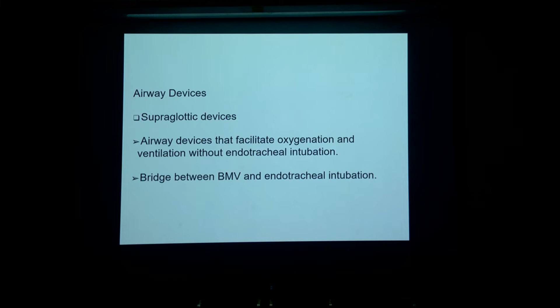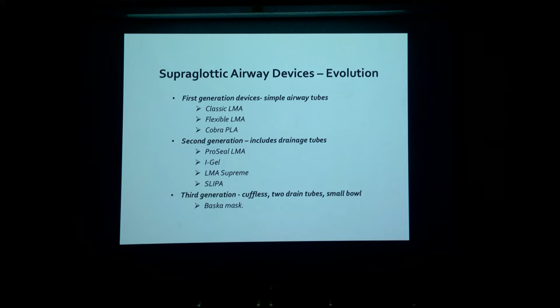The 2nd generation was an improvisation of the 1st generation, wherein disadvantages like gastric insufflation and not being able to decompress the stomach were addressed. And 3rd generation is further better. The advantage of the 2nd generation is that these devices can be used for positive pressure ventilation. But the disadvantage is that positive pressure ventilation should be with physiological PEEP levels. It cannot handle higher PEEP levels. Up to a PEEP of 6, 7, it should be okay. And the 3rd generation, the Baska mask. I don't know how many of you have seen a Baska mask.